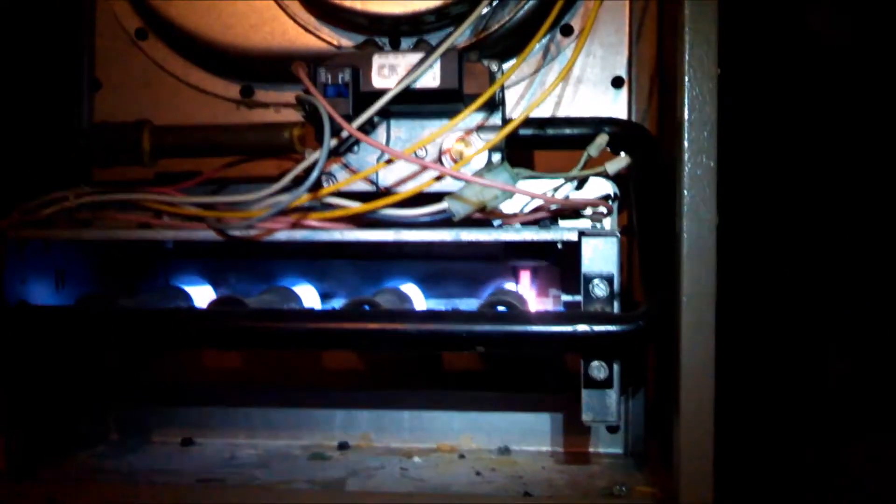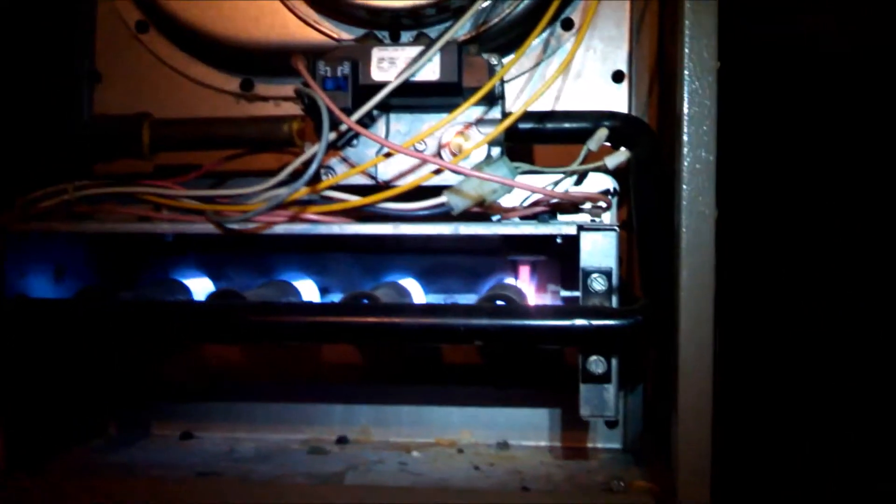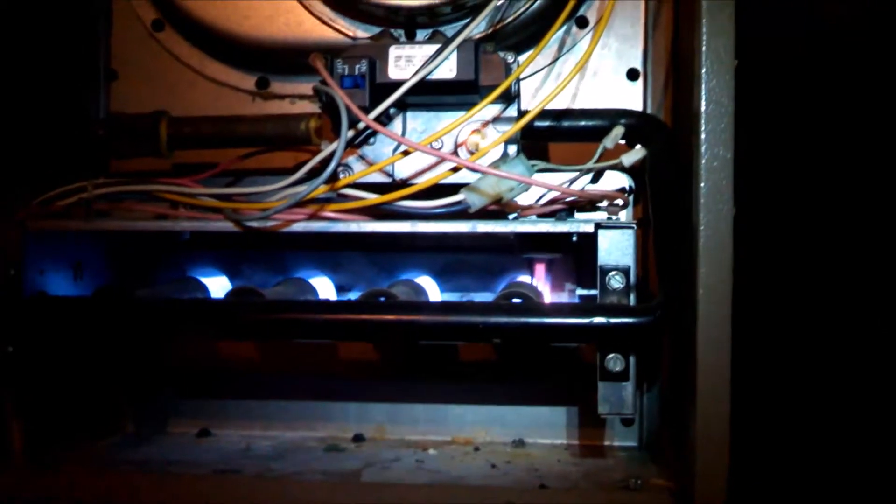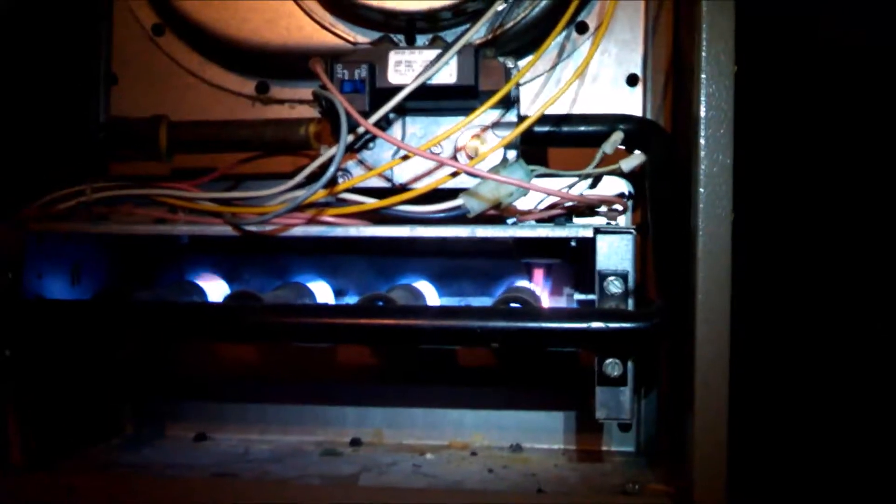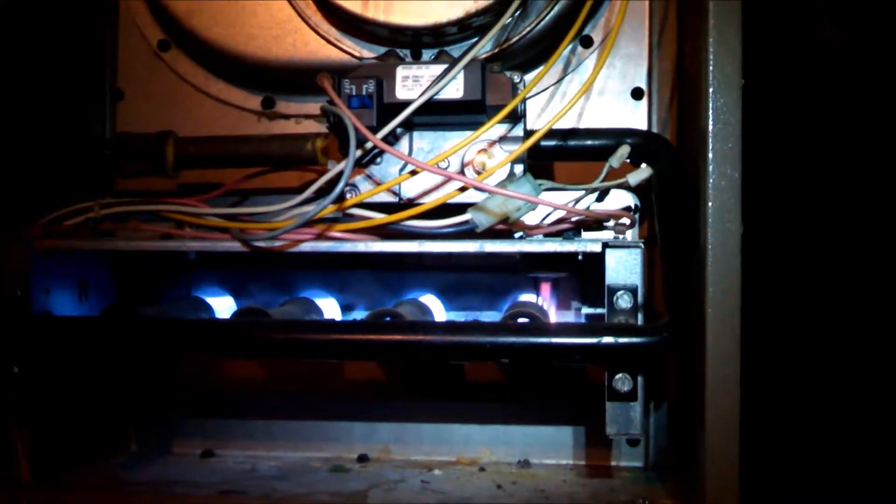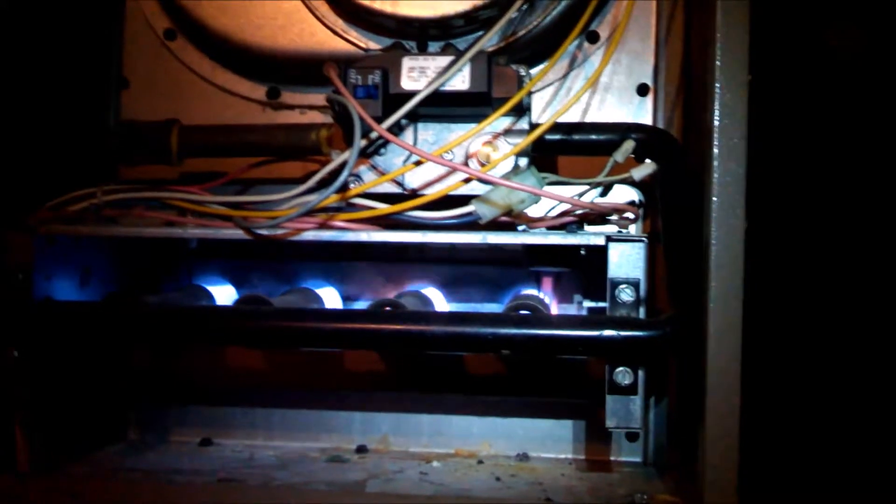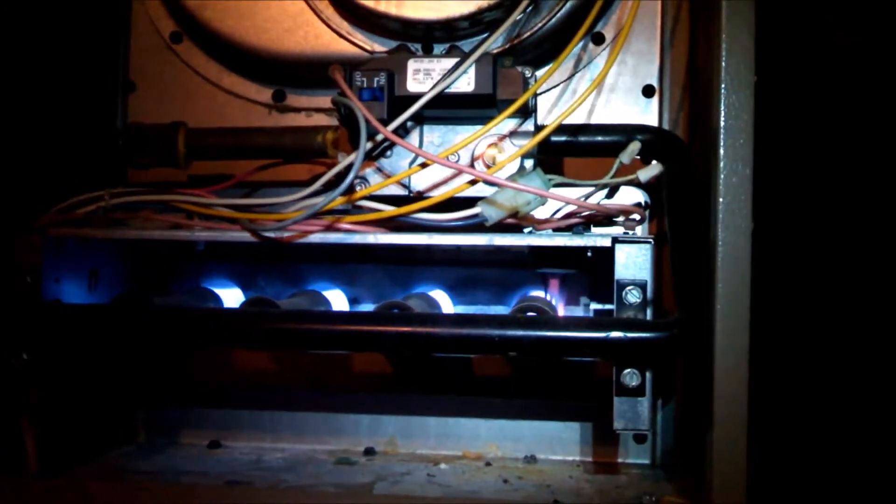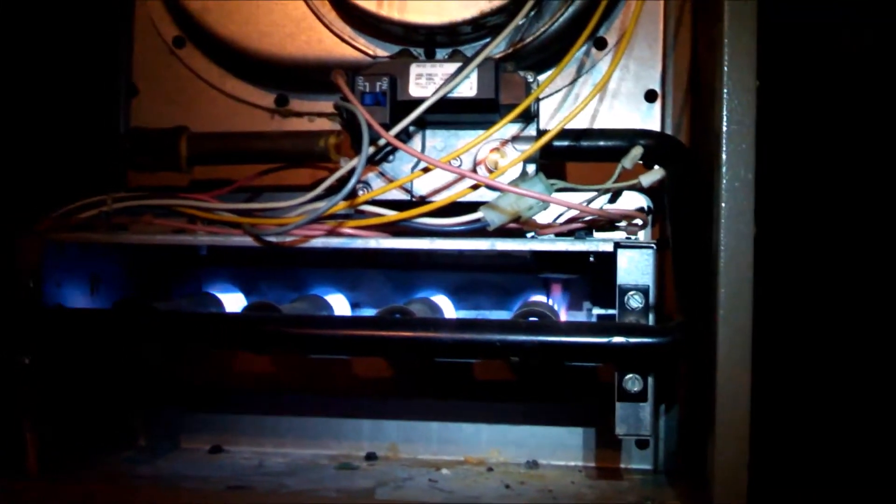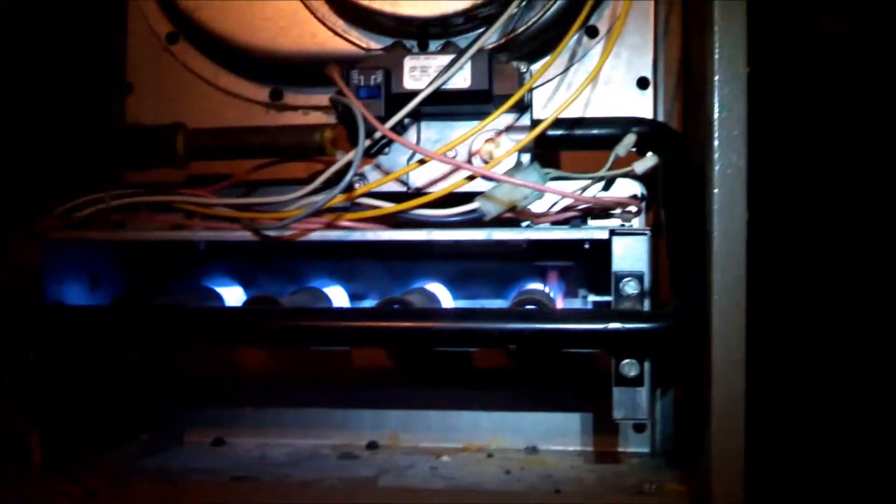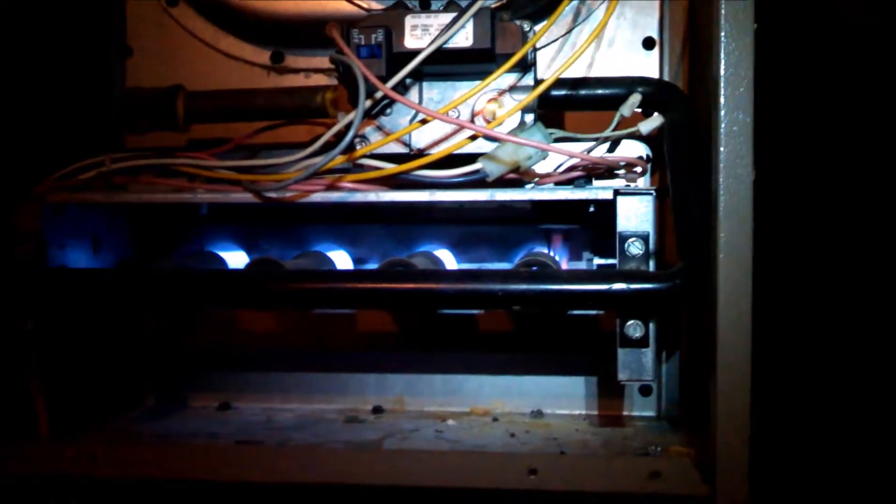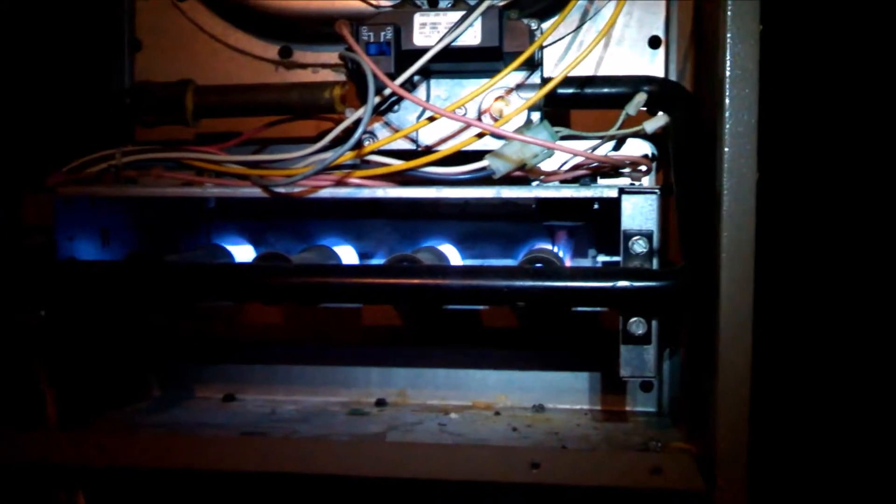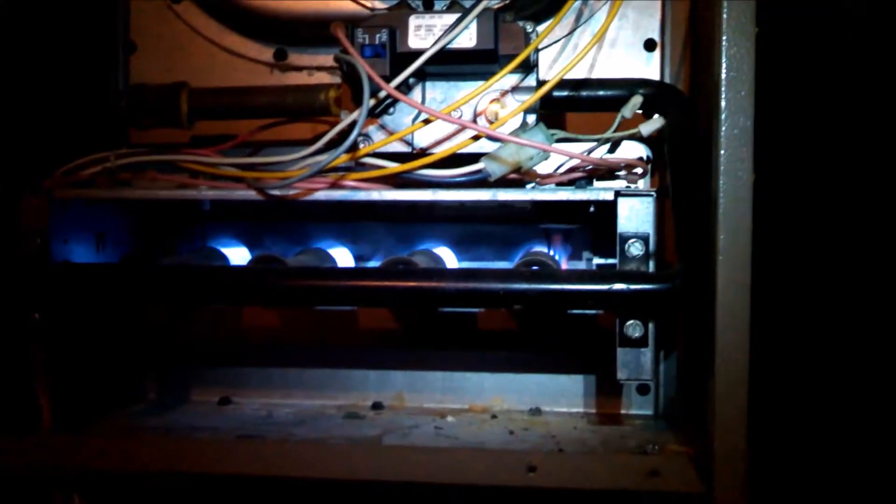I'm going to try a different igniter. This is the first time I kicked this on before I was taping. The igniter glowed. I heard the gas valve open and the gas release, but nothing lit. And then it shut off. And then the second time, by that time I had my camera out, it lit.